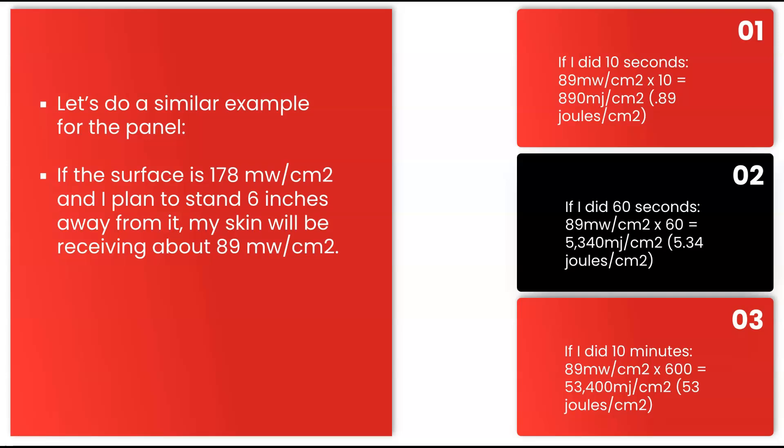These numbers should be given to you by the manufacturer. If the surface is 178 milliwatts per centimeter squared, and we plan to stand 6 inches away from it, our skin will be receiving about 89 milliwatts per centimeter squared. If we did 10 seconds, that would be 89 milliwatts per centimeter squared times 10 seconds, equaling 890 millijoules per centimeter squared. If we did 60 seconds, 89 milliwatts per centimeter squared times 60 seconds equals 5,340 millijoules per centimeter squared, or 5.34 joules per centimeter squared.